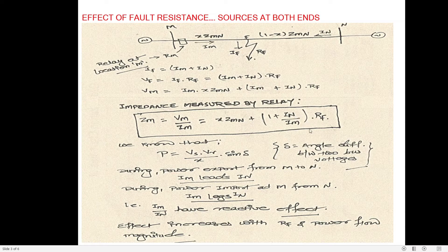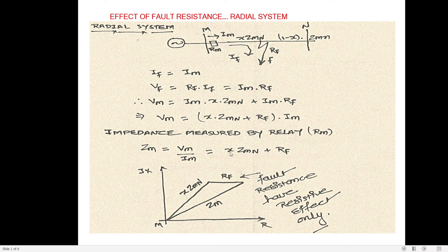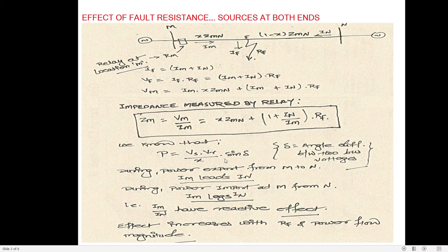Calculating the impedance measured by the relay using the same method, the result is: Z_measured = X·ZMN + (1 + IN/IM)·RF. The only difference from the radial case is the additional term (IN/IM)·RF.